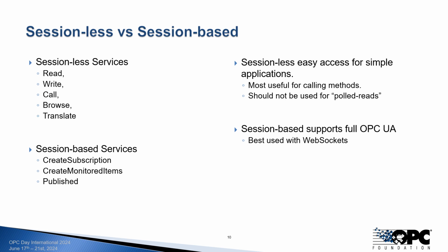The sessionless services are useful for a number of simple applications. In particular, the call service gives you a standard way to extend an information model in order to add custom behaviors, and they're well suited to invocation with a sessionless service call. Browse and translate and read can be used as well, depending on what you're trying to do. You should not be using the sessionless services for anything that looks like a subscription, because doing polled reads on a sessionless service, you're going to run into performance issues depending on how fast.